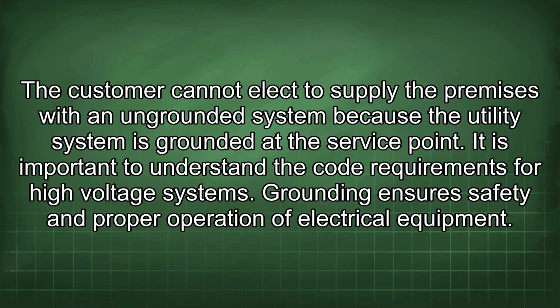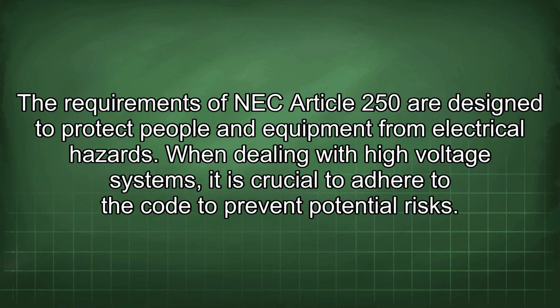The customer cannot elect to supply the premises with an ungrounded system because the utility system is grounded at the service point. It is important to understand the code requirements for high voltage systems. Grounding ensures safety and proper operation of electrical equipment. The requirements of NEC Article 250 are designed to protect people and equipment from electrical hazards. When dealing with high-voltage systems, it is crucial to adhere to the code to prevent potential risks.